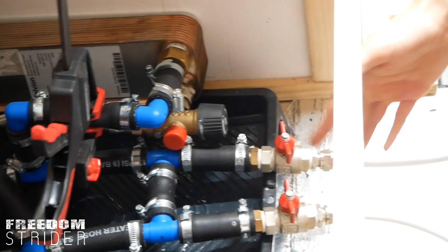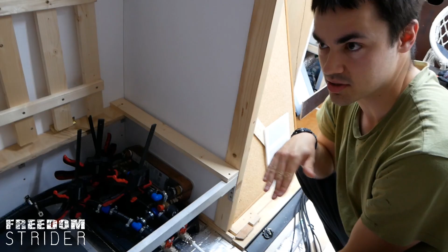So what ends up happening is these two, the entrance and exit of the underfloor, get hot through conductive heat from over here, but the further away you get, the cooler it gets. So the glycol in these pipes is not circulating. What we're hoping is if we put this valve in place of that H and basically shut the valve, the glycol's only path when we want the underfloor on is to run through the entire underfloor system and come out the other side. So let's do that.